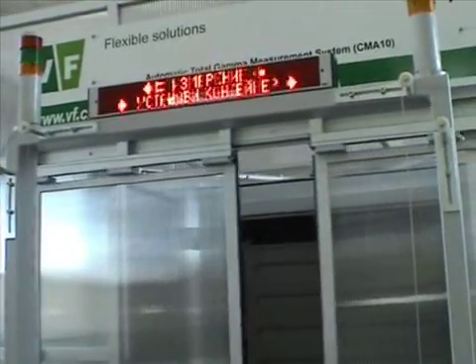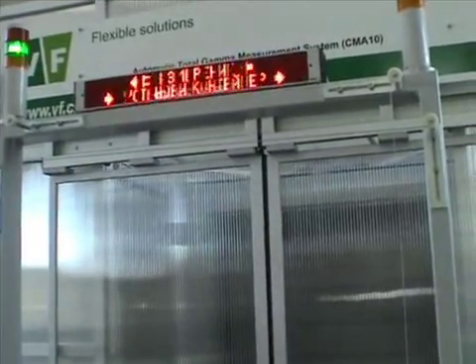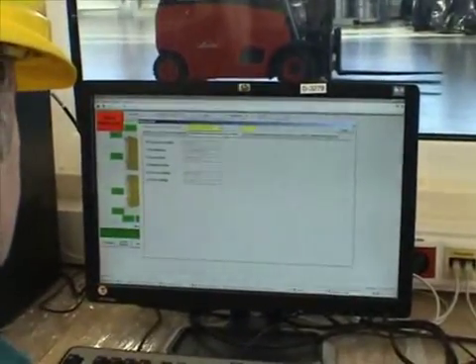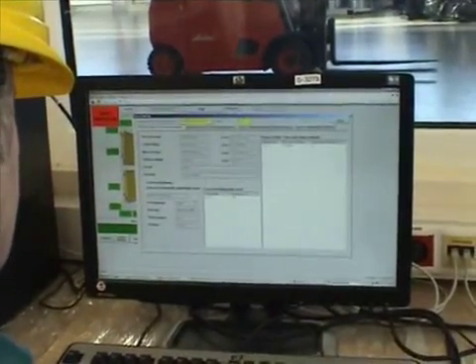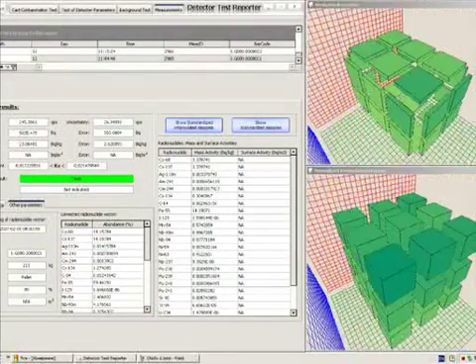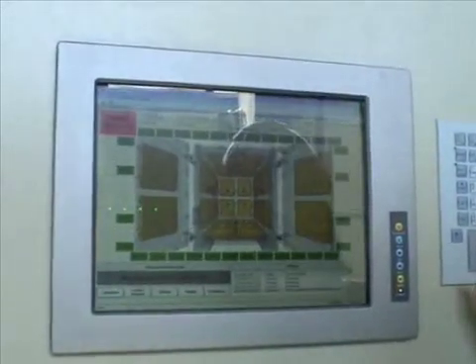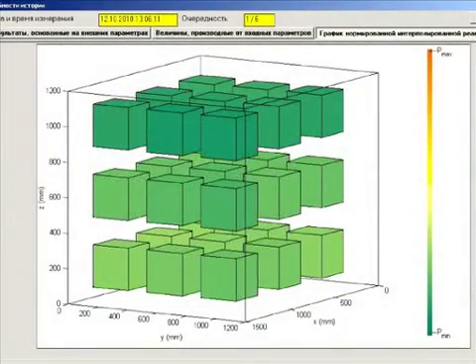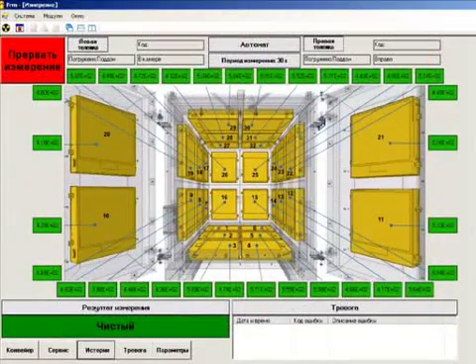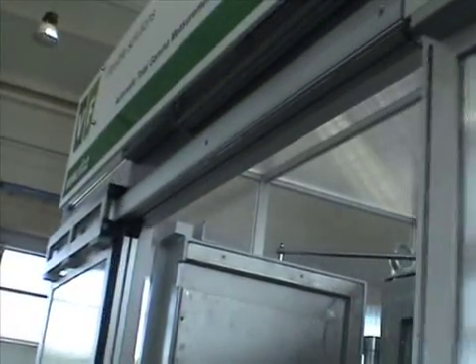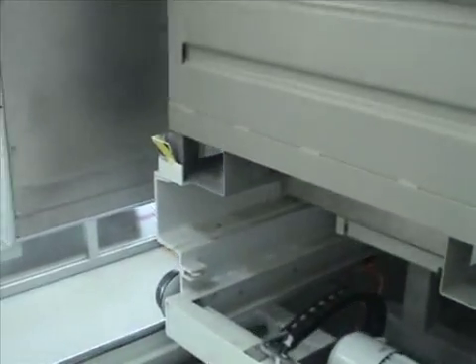As soon as the container is inside the chamber, the doors are closed automatically. The measurement of the total gamma activity of the waste in the container starts. The measurement process can be controlled by a remote computer in the control room with appropriate application software, and also by an on-site computer built into the measurement facility. The measurement is complete. The information display shows the measurement results: clearance granted — meaning that, based on the results of calculations, the specific activity of the waste is within the free release levels and that such waste may be released and reused.